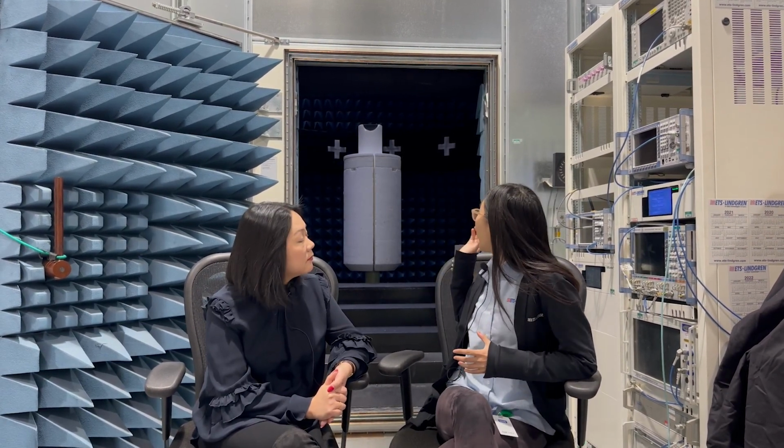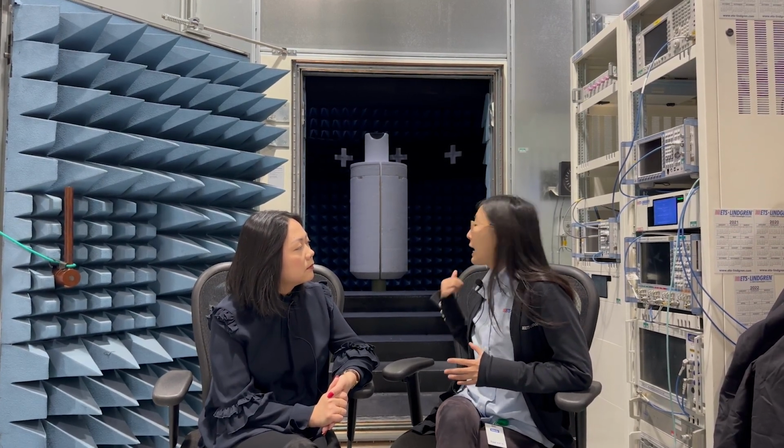Speaking of the chamber components, these are the 12-inch absorbers. The antenna array we're using here is the 3165-05. That antenna goes to 7.2 gigahertz, but we can support other types of antenna; generally this chamber is designed for frequencies from 400 megahertz to 10 gigahertz. And we have this single axis positioner, the 2006, here. This is a pretty comprehensive package we can put together for the customer.